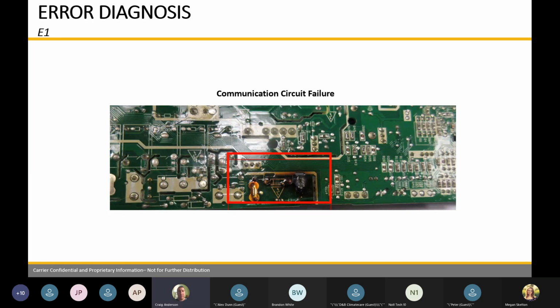Another communication failure, a wiring issue. They went in, they mixed up the wires from the indoor to the outdoor unit. They had L1 on S. As soon as they powered that up, they put 120 volts to S and they fried something. So wires need to match up, very critical.